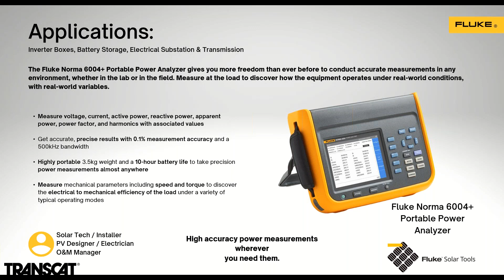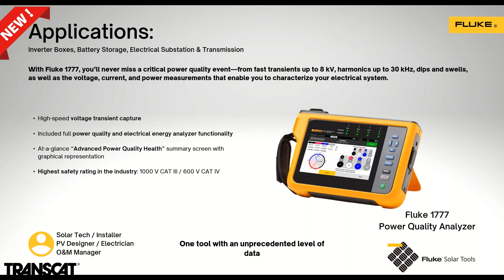Now the 1777 is an incredible tool on that AC side. Being able to look at harmonics and transients, again, that capability on the AC side, and determining what that output looks like. And this can even go farther, even after the inverter. You could be doing these types of measurements through the step-up transformer just to determine that the transformer is also working correctly. Let's go to the next one.